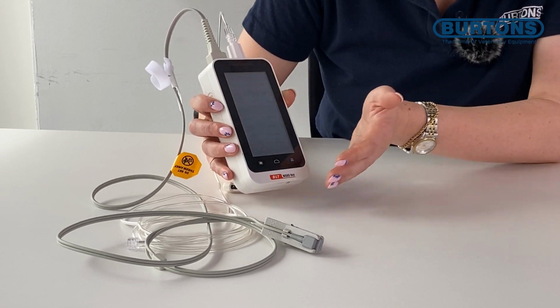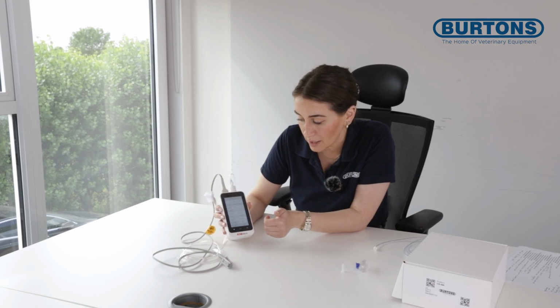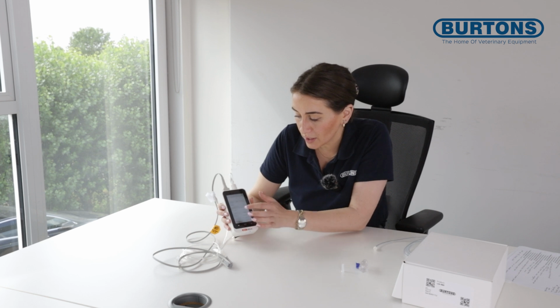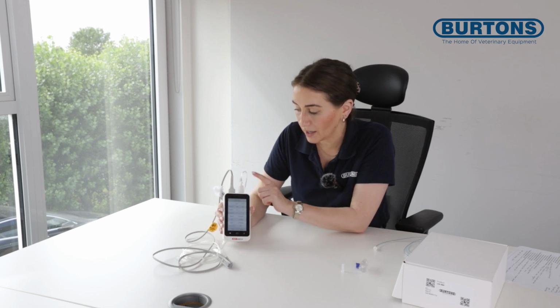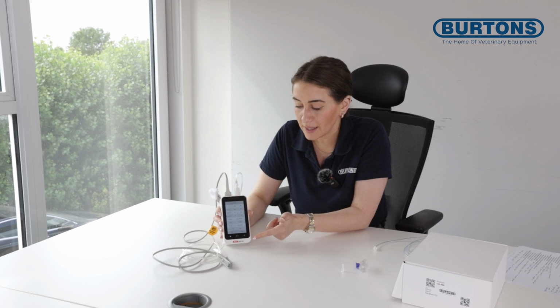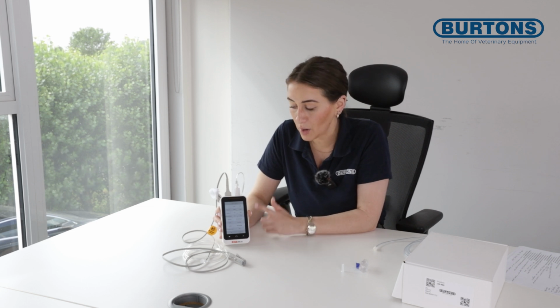So every alterable setting that you have on a multi-parameter monitor, you can also alter within here. And it's just important to note that if I'm not using CO2, that I plug out my filter and my sample line, because the CO2 is actively pulling from my patient's breath. So when I'm not using it, to preserve the internal module of the CO2, I'm better to remove this so that it's not pulling and actively working the module, and preserve the life of the module. So if, for example, you're in recovery, your patient's extubated, and you just want to use the SPO2 probe, it's worth disconnecting that and placing it back in the box to preserve the life of the module.